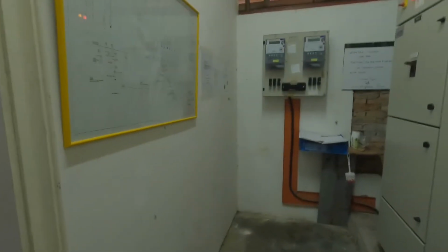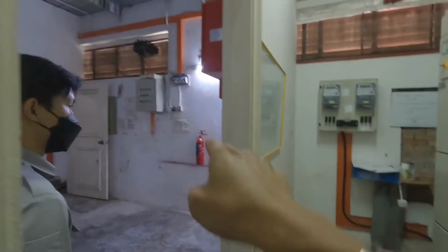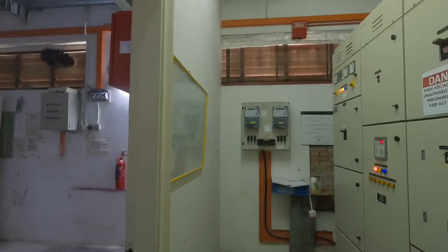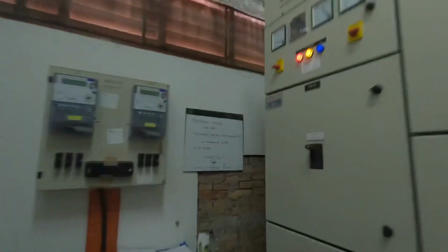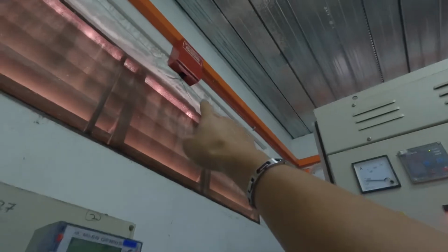Okay, now as we go inside this LV room, according to regulation, mesti ada fire extinguisher. So this fire extinguisher CO2 supposedly kena pasang sini sebelah pintu or here. Okay, so that one CO2 fire extinguisher. Okay, then later on inside this LV room we have fire curtain. Okay, correct, there's a fire curtain available, firefighting system available, no problem. Okay, logbook, meter reading, everything available for reference.